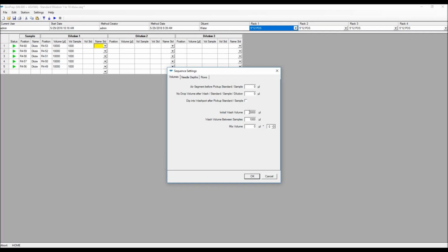And like I said, your rinse is totally user configurable, so that's all in your hands. There's the initial volume, which essentially acts as a prime, and your volume between samples, which is where your rinse usage will come in. And that is a dispensed value. So it rinses the inside of the probe because it dispenses that volume out. But also the pump will of course turn on the autosampler. So if you have a rinse solution hooked up there, it will also rinse the outside of the probe that way. So you get kind of a double rinse to make sure that things get really clean.